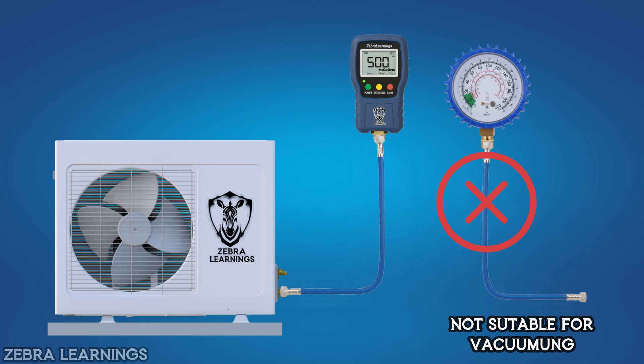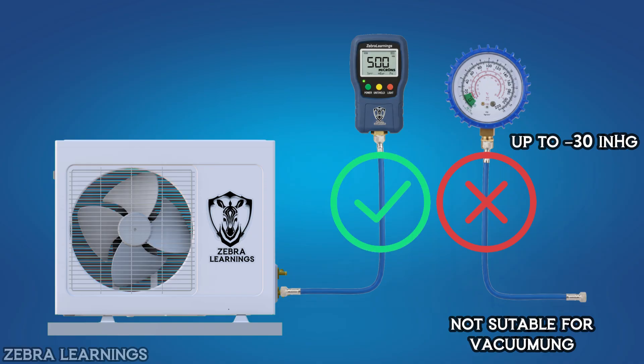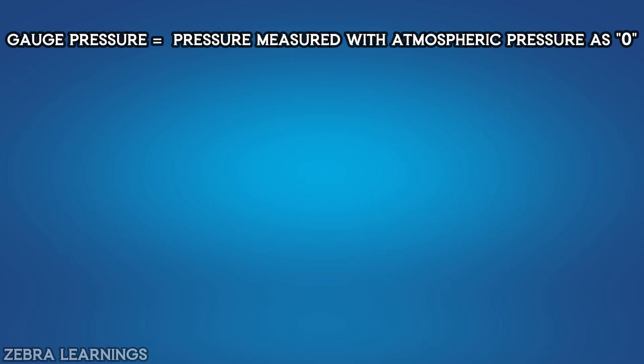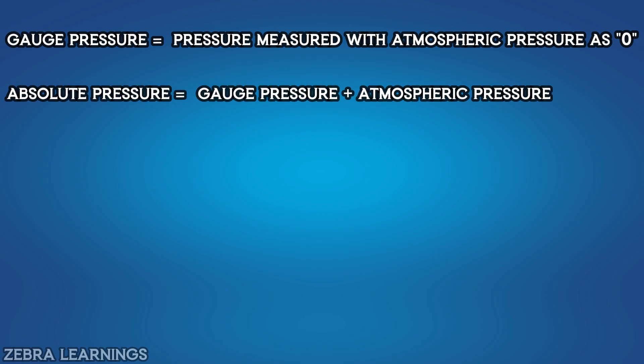The manifold gauge can show only rough vacuum values, up to minus 30 inches of mercury, but to know the exact deep vacuum, we must use a micron gauge. That's why we say: gauge pressure equals pressure measured with atmospheric pressure as 0, and absolute pressure equals gauge pressure plus atmospheric pressure.